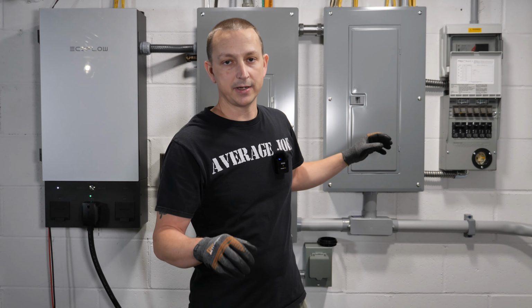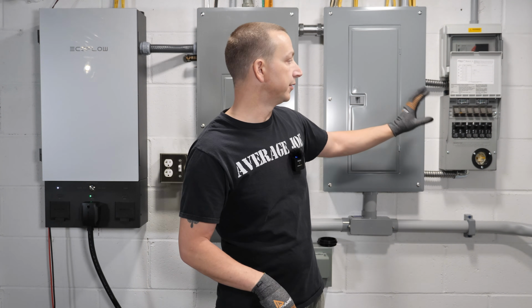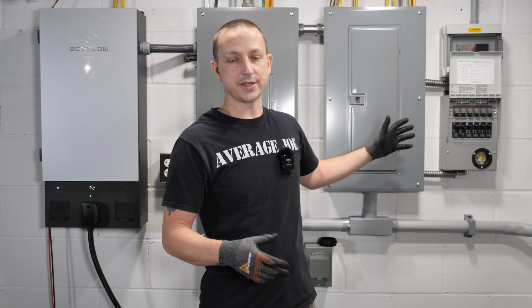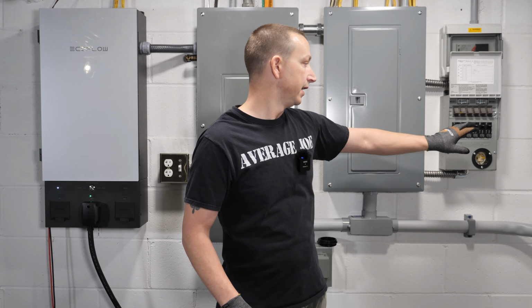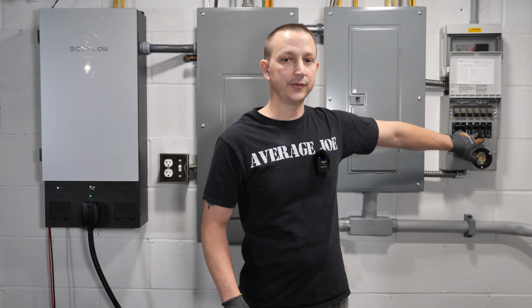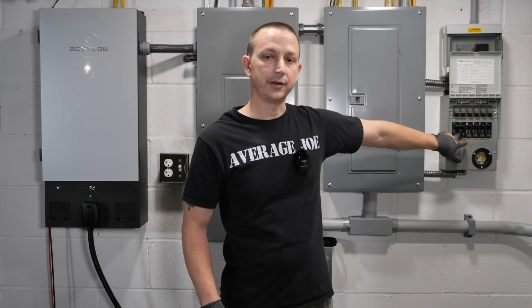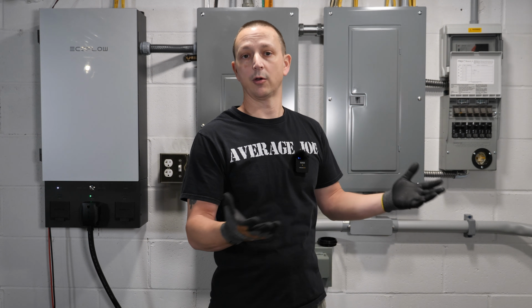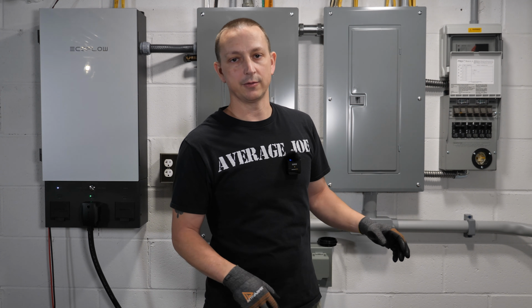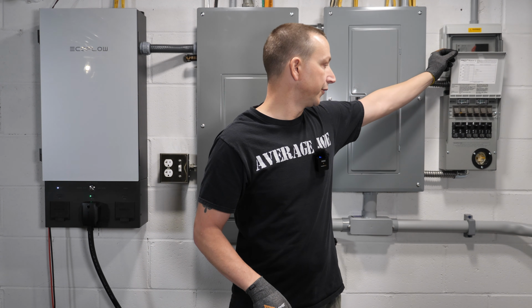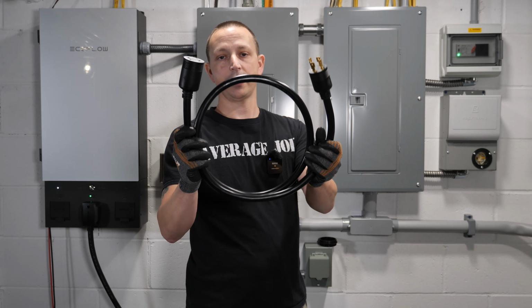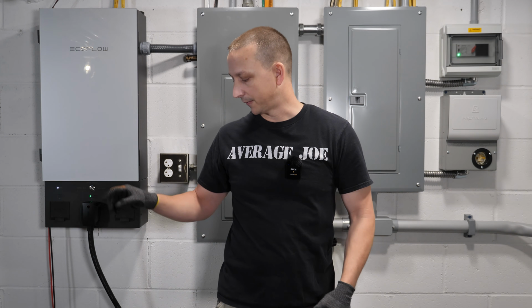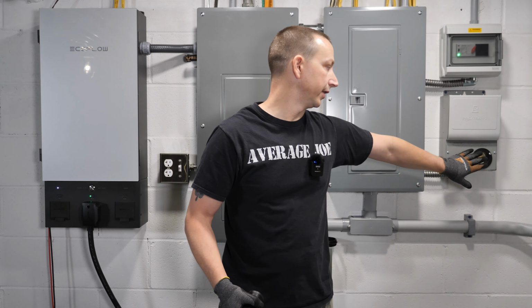I know there's many different models out there, but this is just an example. You would use something like this in an emergency where you just needed to power a couple of circuits. This one has 4 120 volt circuits and 1 240 volt circuit, for like a well pump or really anything that you would need 240 volts. To connect that, you would use your 30 amp generator plug right off the front of the inverter, and you just plug it in right there.